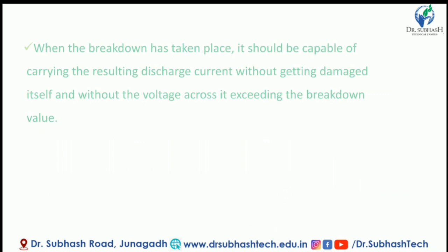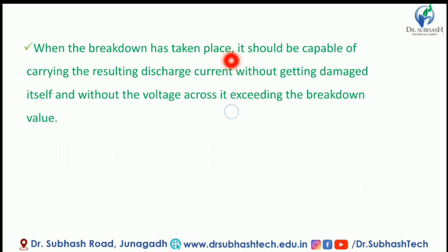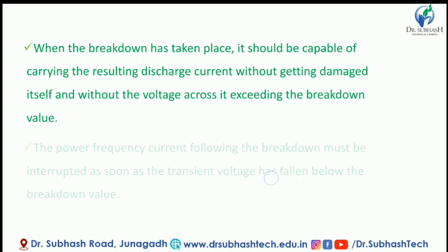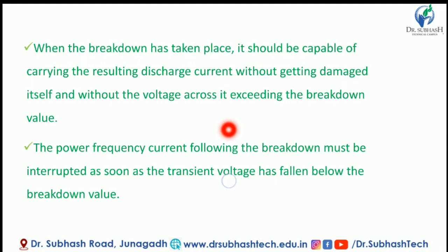Once breakdown has taken place, it should break down as quickly as possible and be capable of carrying the resulting discharge current without getting damaged itself, with the voltage across it not exceeding the breakdown value. The power frequency current following the breakdown must be interrupted as soon as the transient voltage has fallen below the breakdown value.